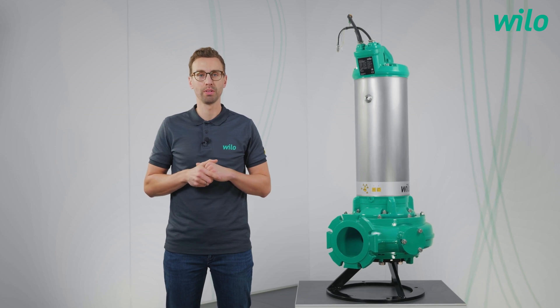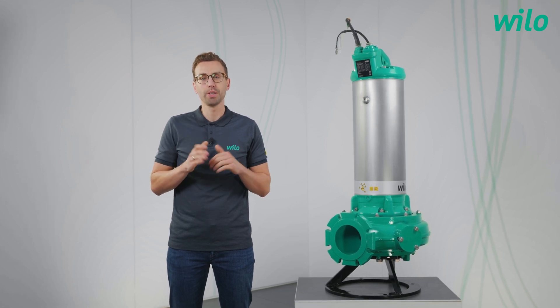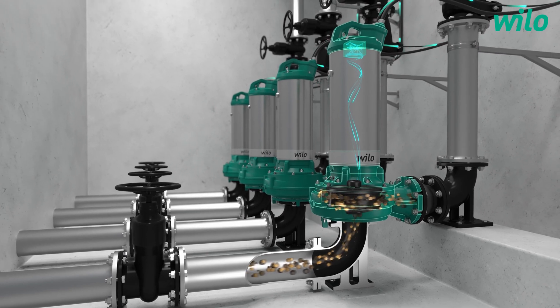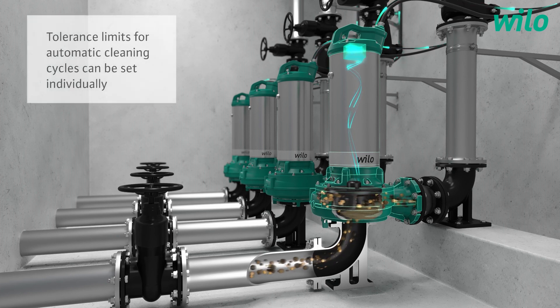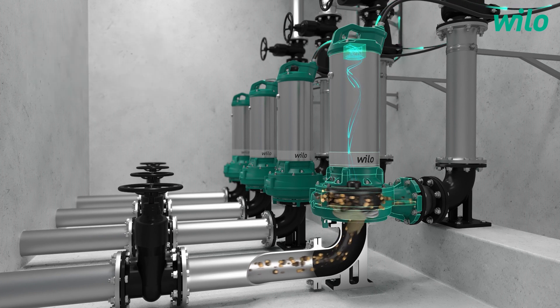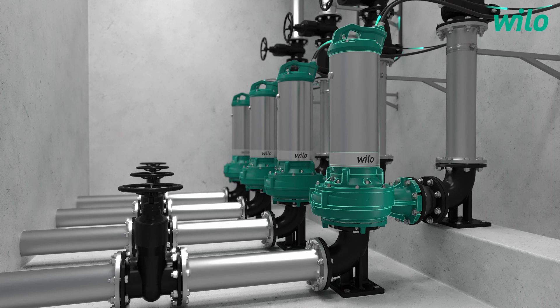Thanks for the quick overview. I think the daily work could be easier for our customers when they use our product. Could you explain operational reliability? For high operational safety, the pump has the highly reliable REXA Solid Q hydraulics with an integrated groove in the suction port for a guided way for solids through the hydraulic. Additionally, the Nexos Intelligence detects solids in the hydraulics early and prevents clogging. Automatic cleaning cycles, which are especially made for our hydraulics, help to solve clogging problems. Herewith, operational safety can be increased and expensive downtimes and service calls can be avoided, for example on weekends or on holidays.